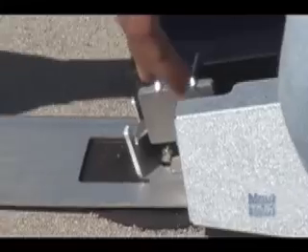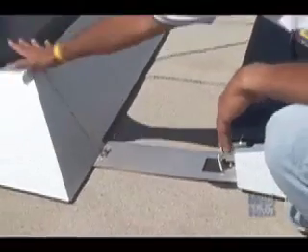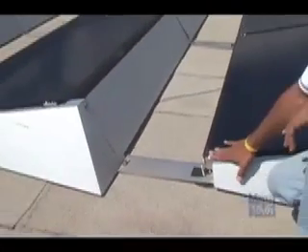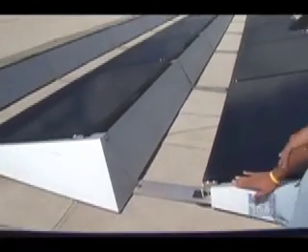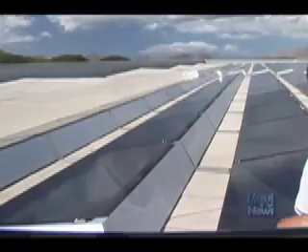What it is they are all interconnected side to side and front to rear, and they use a ballast as well as the design of the deflectors that are on the north, east, and west sides help to keep wind from getting underneath that. The ballast creates enough weight to hold this array. They've both seismically tested this design as well as wind tested this design, and we've provided documentation to the county, and they've accepted and signed off on that.